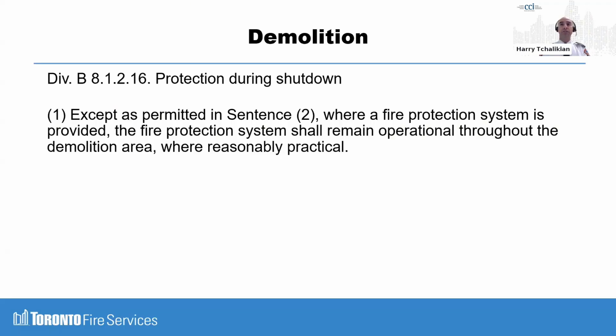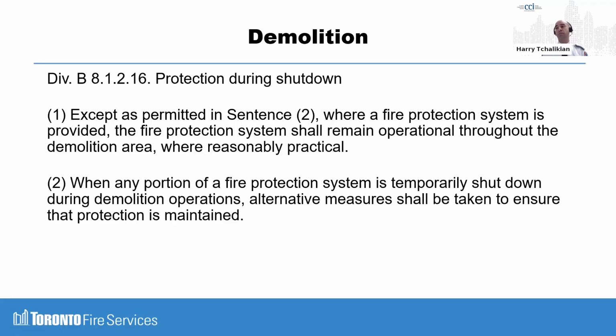Next, protection during shutdown. Except as permitted in sentence 2, where a fire protection system is provided, the fire protection system shall remain operational throughout the demolition where reasonably practical. And 2, when any portion of a fire protection system is temporarily shut down during demolition operations, alternative measures shall be taken to ensure that protection is maintained. Wouldn't necessarily apply to a residential unit being renovated, but it's more applicable to places like retail, like malls, for example. Just make sure you're not disabling any fire alarm device specifically.